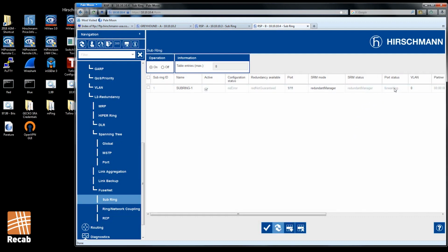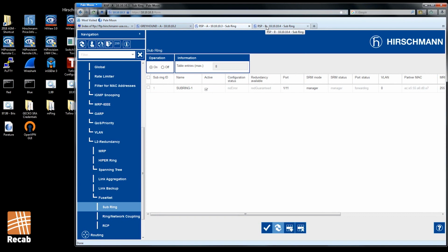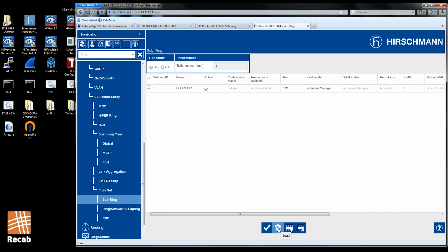So this one's now forwarding, and I'm going to now plug in the other one. And if I now do a refresh on this, this one is now blocked because we now have a ring. And if I do a refresh on him, he is now forwarding. So we have our ring built, or our sub-ring built, and one is forwarding, the other one is blocking.